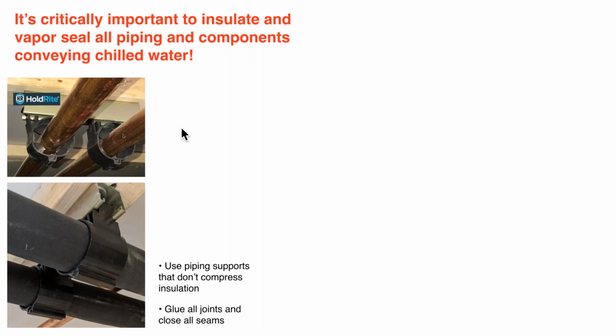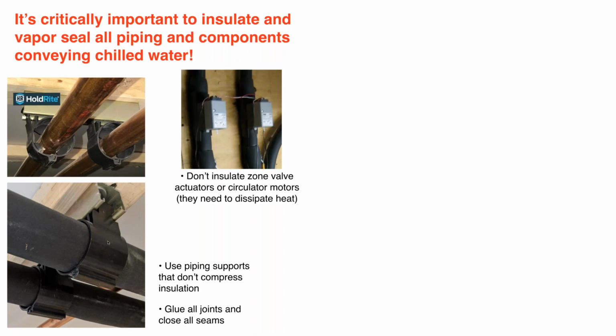This is a product that we've used before. It's a plastic clip made by this company, Holdrite. It goes into some unistrut channel, and there are ribs in here that structurally support the pipe. But the nice thing is you can tuck the foam insulation in on both sides, and you don't see it here, but this should be caulked with silicone all the way around. The idea is that we're not allowing any ambient air to contact that piping, and if you keep the air away from the piping, you won't have the condensation.